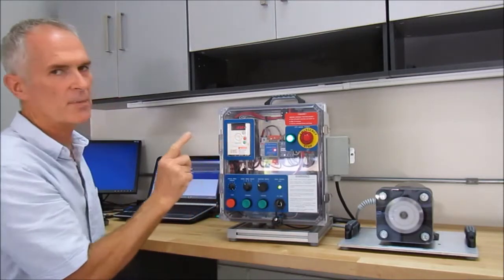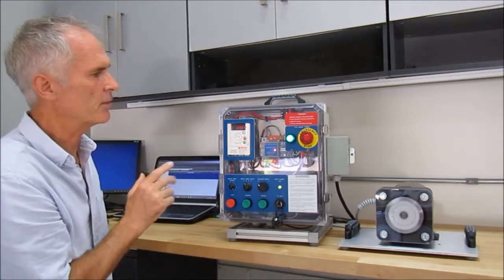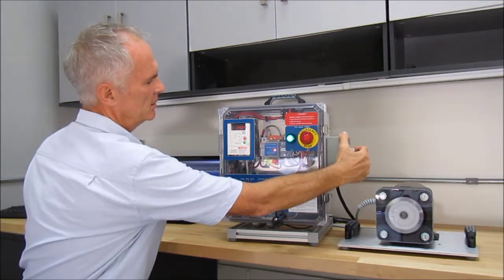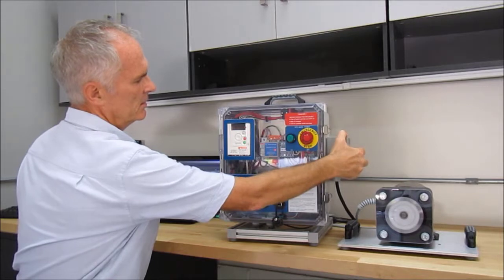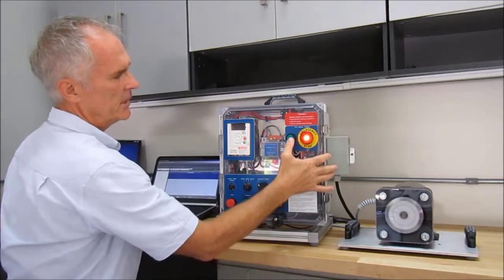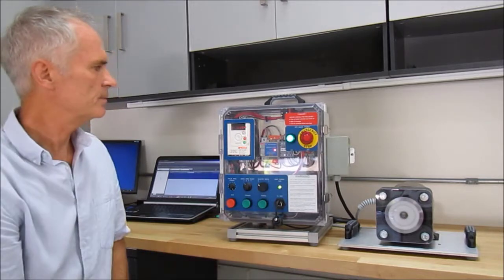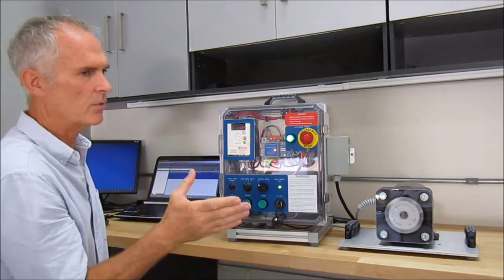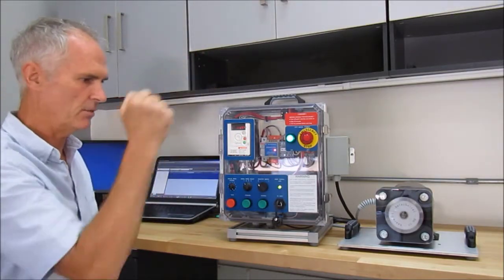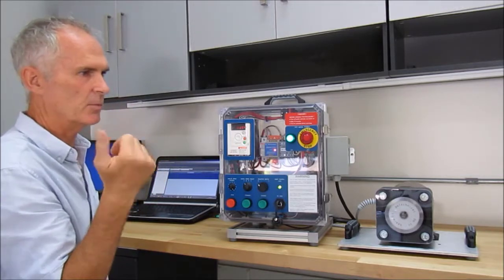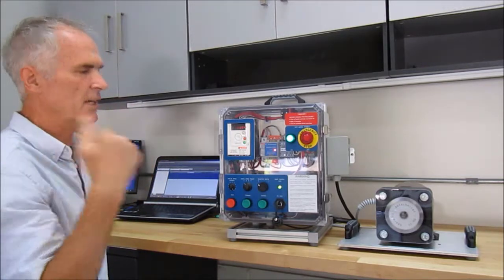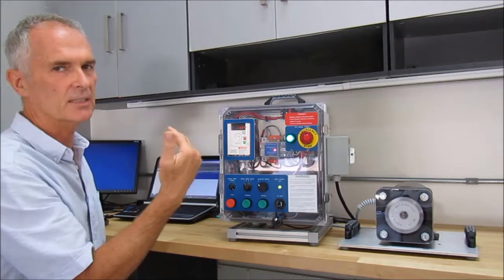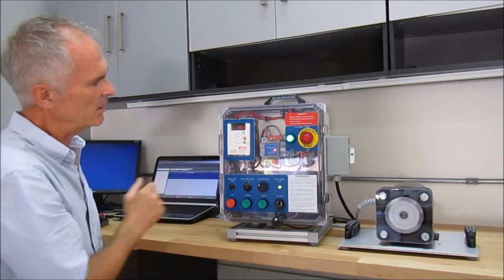Okay. Now this type of control provides low voltage protection. So if there were a power failure, so if I were to interrupt the main supply to the controller, okay, it shows under voltage. I'm going to bring it back on, energize the mains for the motor controller. It's going to start up in a safe condition. So for metalworking equipment like that little drill press that I mentioned, you're drilling away, you have a power failure, or you trip out a circuit breaker, or somebody else trips out a circuit breaker. When they reset that circuit, it will resume power and it will be in a safe position. So I can just go ahead and hit start, and away we go.